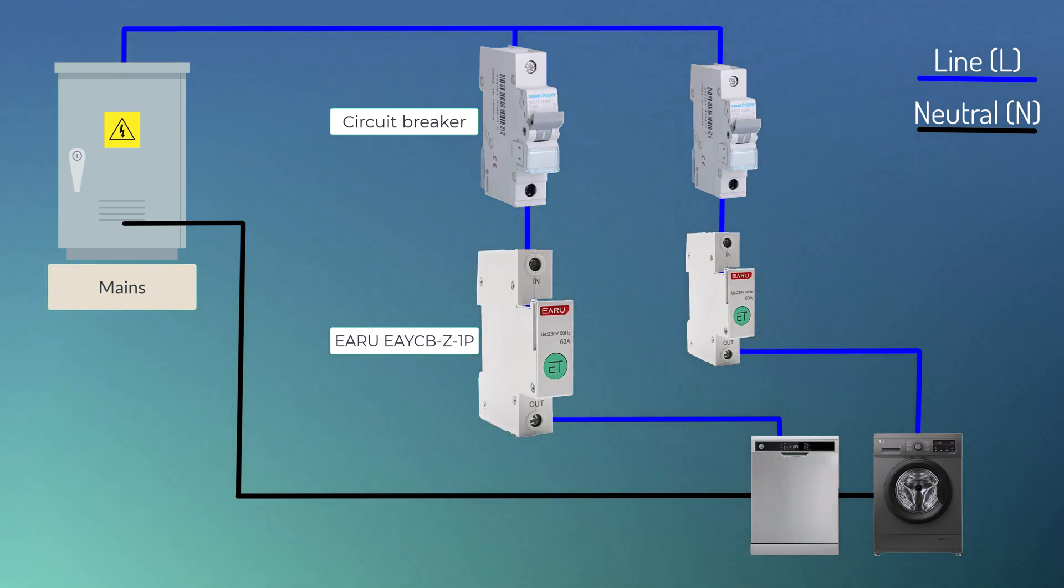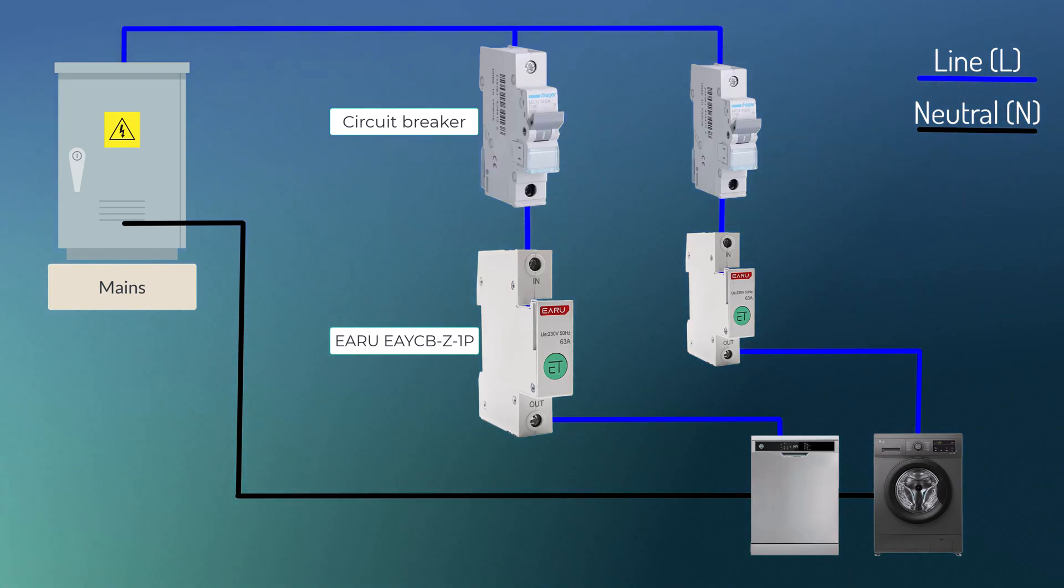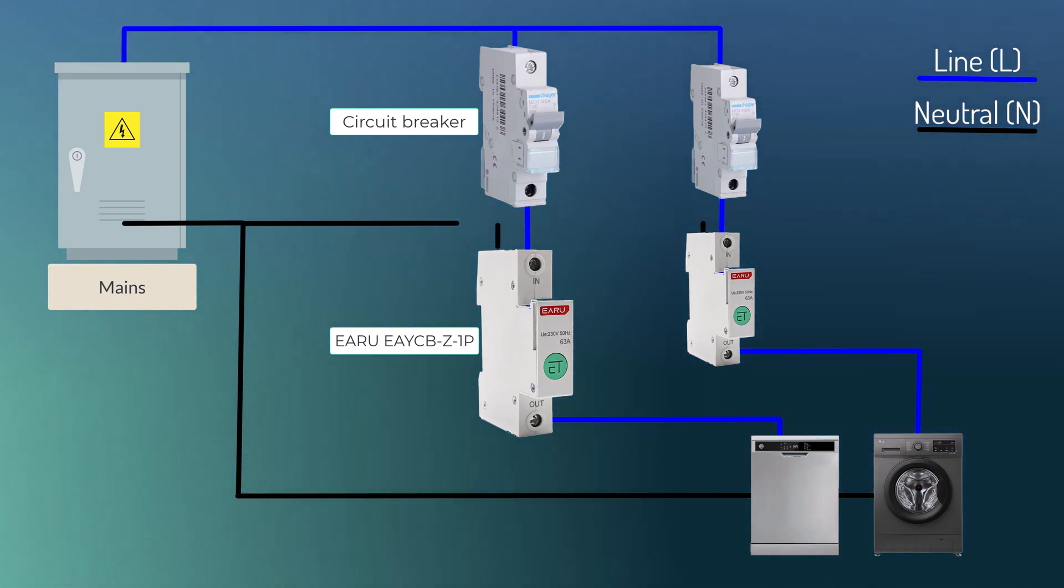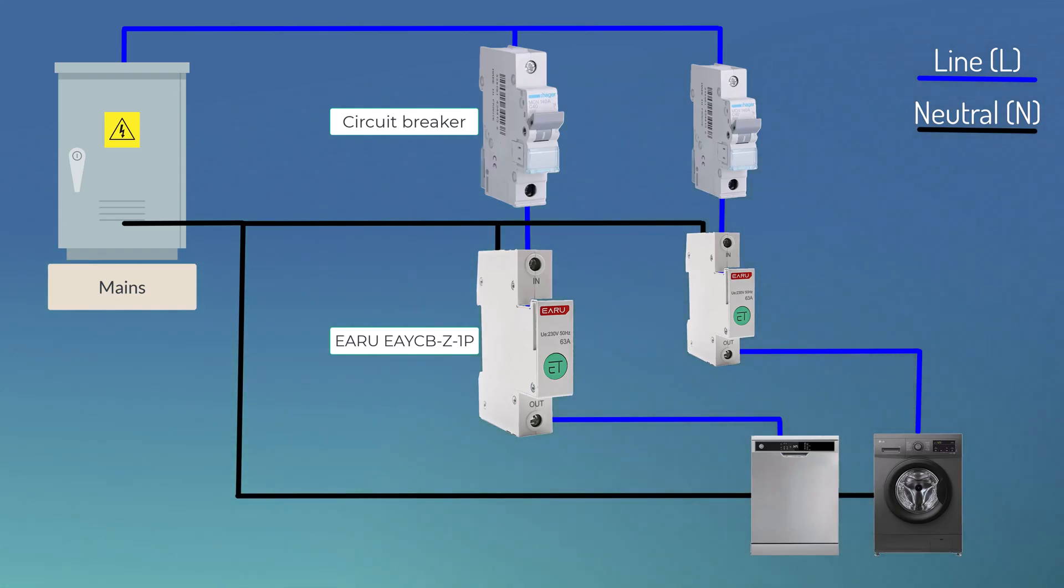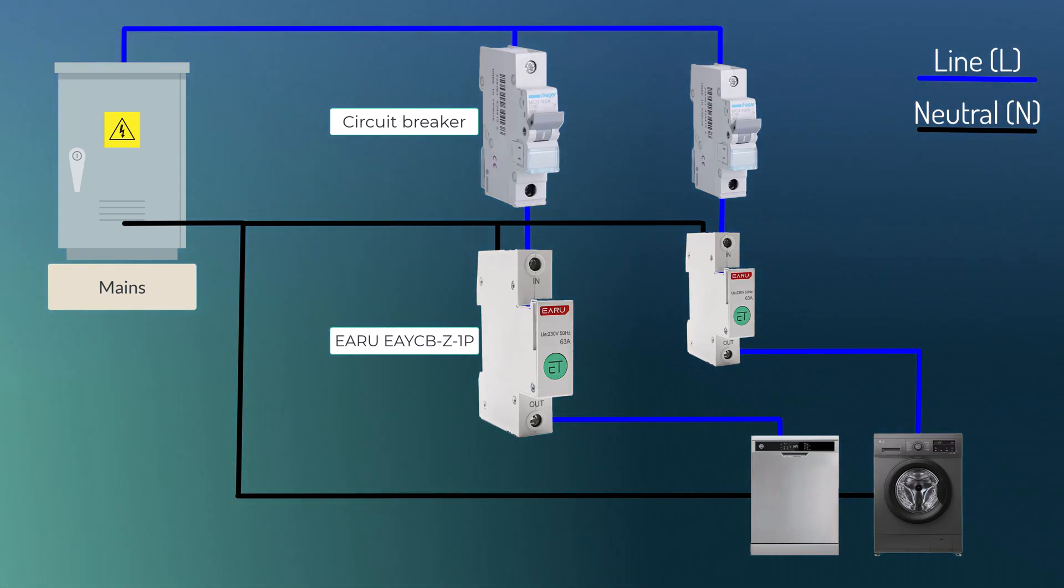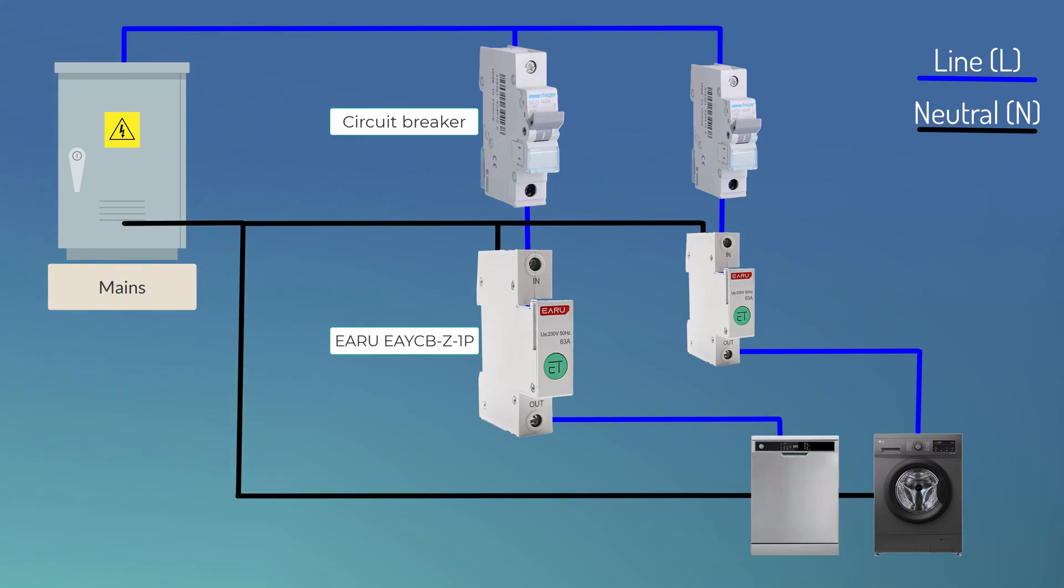What we're going to do is intercept the line with the smart circuit breaker, and then we need to also connect the neutral because this is an active device. It needs to have its own power. So this way we can leverage the previous circuit breaker's reliability and the energy metering from the smart circuit breaker.